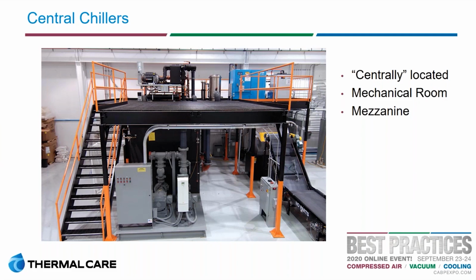This is actually a mezzanine that's inside of the facility, but as you can see there on the top of that mezzanine, that's a central chiller. And then down below there's that large panel with all those indicator lights on it. It has a process pump and then a chiller pump. The process pump pulls water from what would be known as the cold well of that tank. It then pumps that water out to the process or whatever's generating the heat. In some cases, it could be an injection molding facility. It could be a heat treating operation, lasers, you name it. Anything that really generates heat requires some cooling. So this process pump delivers that cooling water to those usage points.